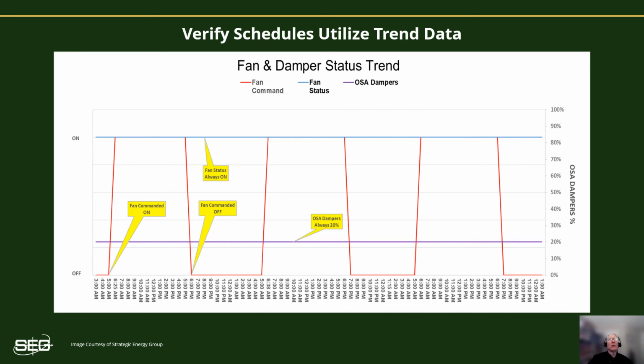In this example, the red represents the fan command and appears to be following a weekly schedule, coming on at 5 and going off at 7. The blue line represents the actual status for the fan, and it seems to be stuck on, never shutting off. The purple line represents the outside air damper command, and it's set for 20%.